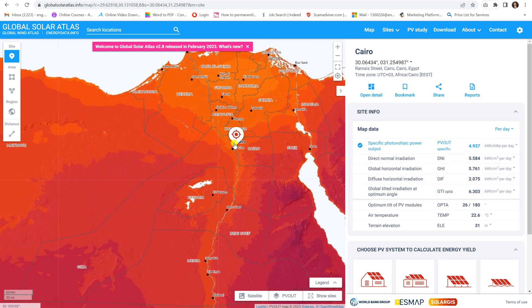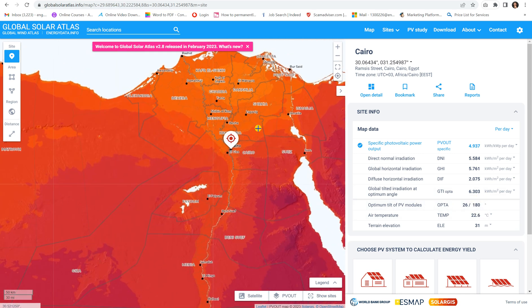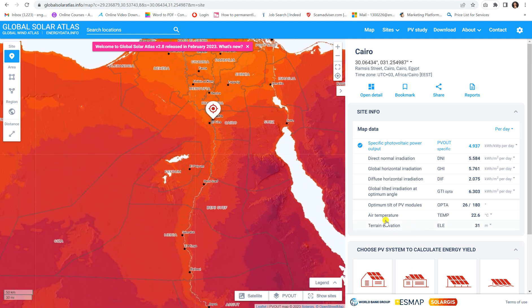For this location, the Global Solar Atlas tells you that the optimum tilt angle of the PV modules is 26 degrees — this is the optimum angle calculated by the simulation. The azimuth of 180 degrees means our panels face south, since Egypt is in the northern hemisphere. You also see the air temperature of the surrounding area and the elevation of the location.